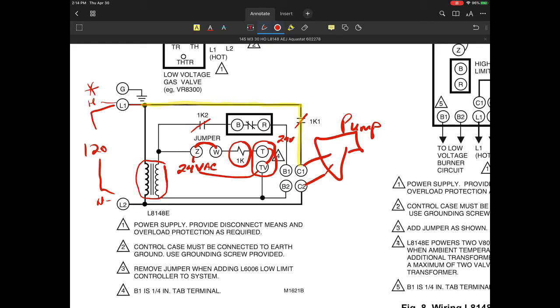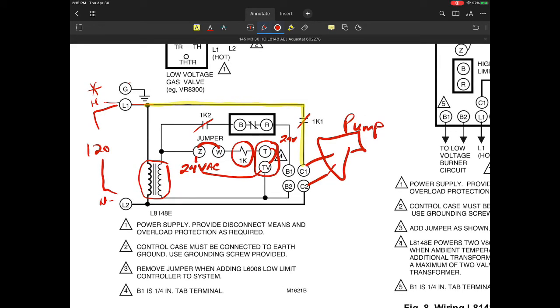It really becomes a little bit challenging to some extent, because if you took a jumper and went from terminal Z to the chassis ground, you could actually ground that individual transformer. Generally, I never see this done in the field. My point in telling you that is that if I went from the chassis ground to Z or to T or to TV, it's a floating voltage. It's not tied together anywhere, which would give you these kind of bogus numbers. No matter what side you check it on, you may be getting 24, 26, 28 volts. You might be picking that up. So that's just something to note from a diagnostic standpoint.